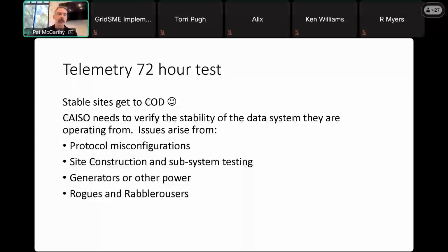What CAISO wants to see at the end of a 72-hour test, which comes some time after your point-to-point test, not necessarily immediately after, is 72 hours of perfectly good data. Other reasons people can fail this 72-hour test are some protocol misconfigurations. Again, inverter stuff can. Inverters that weren't part of the point-to-point test coming online and feeding into a power plant controller might not be configured right, and they can cause problems. You can have things like deadbanding that just overfill buffers and cause dropouts.